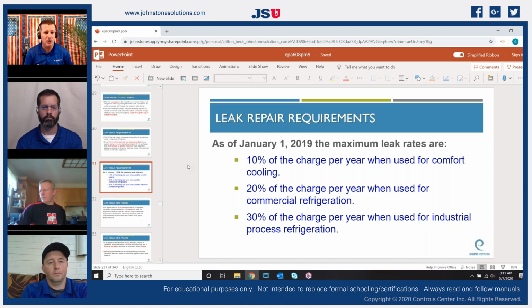So if we're just talking about comfort cooling, if it is for air conditioning, it has a 10% leak rate. So if it's a system that has 10 pounds in it, if it's leaked 1 pound, we now have to go find that leak and we have to document it. If it is a system that is used for commercial refrigeration, so say it's being used for running coolers and running freezers, we know that that's not really an air conditioning system, but it is now going to be a refrigeration system that is in our field.